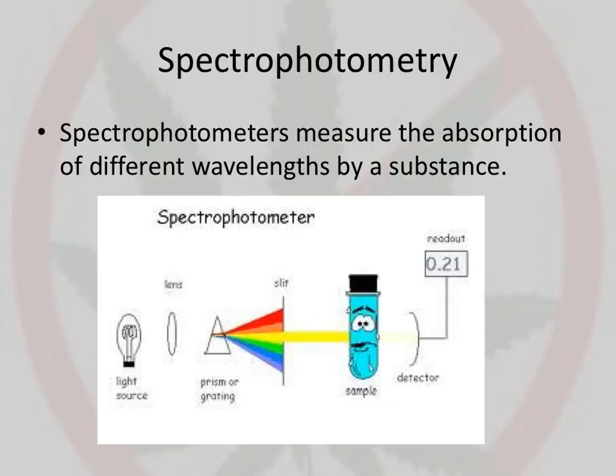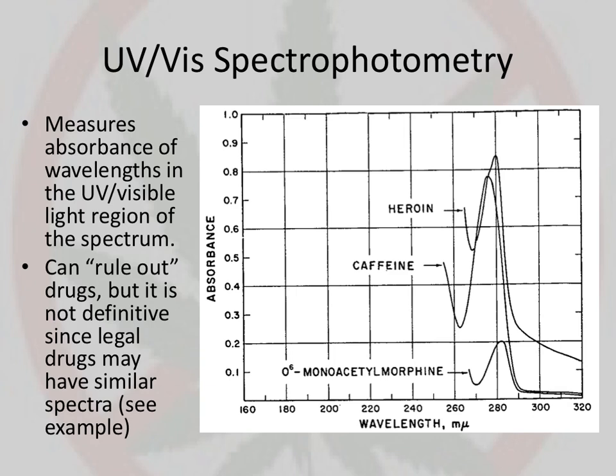A spectrophotometer literally just measures the amount of light that gets absorbed at different wavelengths of some substance. You have some type of light source that gets focused so you can use a slit to specifically choose what wavelength you want to look at. It shines through the sample, and then the detector detects how much light gets absorbed versus how much light gets transmitted through the sample.